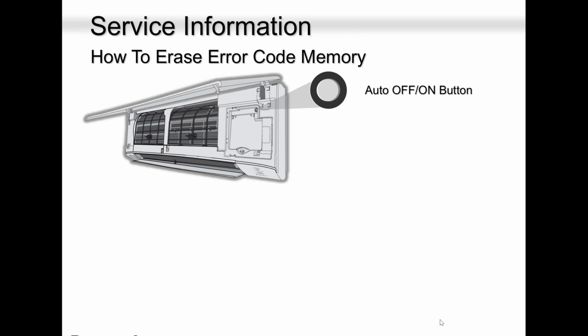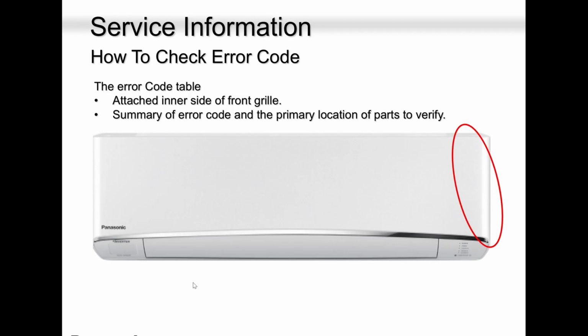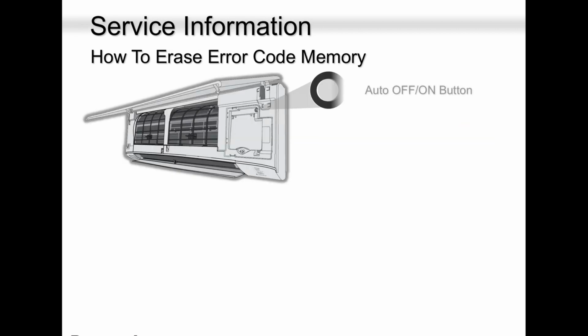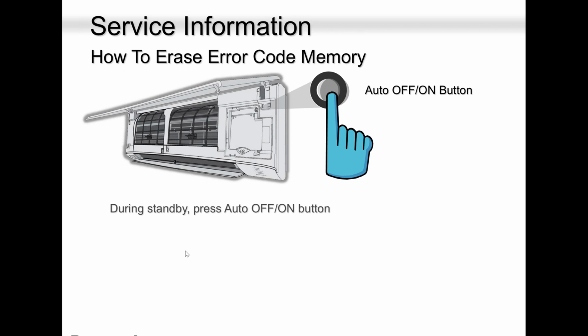Then when you fix the error, okay guys, when you fix the error code, everything is up and running, don't just take off. Please don't take off. Please erase the error code, and it doesn't take more than 5 seconds. All you need to do is, when the unit is closed like this, open it. Press that button. There is a push button there. Press it and hold, and you will hear one beep.